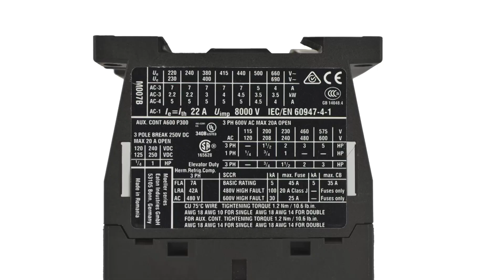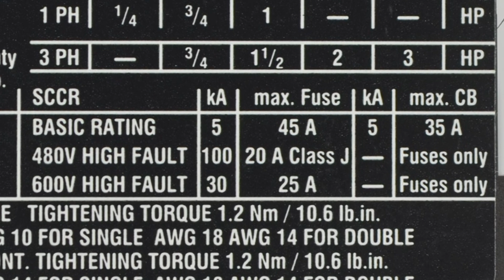of protection. An example is this contactor with a 5,000 amp default short circuit current rating. However, this same contactor has a 100,000 amp short circuit current rating when protected by a max 20 amp Class J fuse due to its current limitation. It is a serious safety hazard and misapplication to apply devices beyond their short circuit current rating. Let's take a look at what can happen.